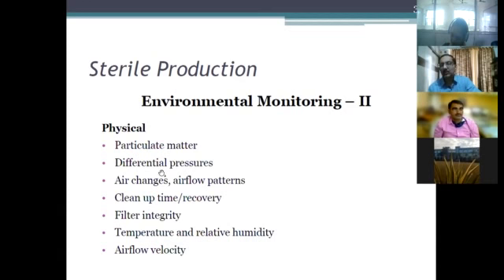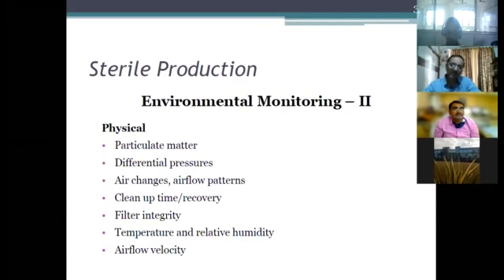Differential pressures are required so that whenever any door is opened, the air from outside does not enter inside. So there is a differential pressure. The most critical operation is carried out under high pressure. So there's a lobby and there's a filling room. The filling room is under positive pressure, the lobby is under negative pressure. So if the door is opened, air from the lobby does not go into the filling room. Air from the filling room may go out into the lobby.